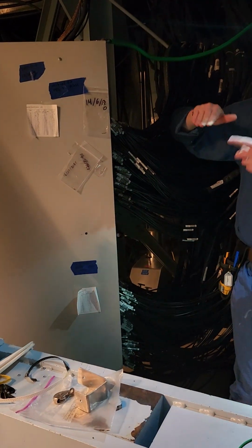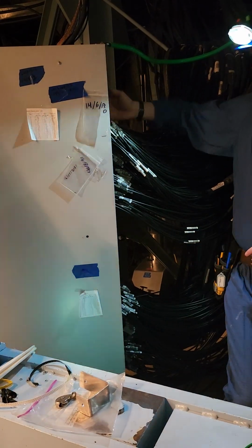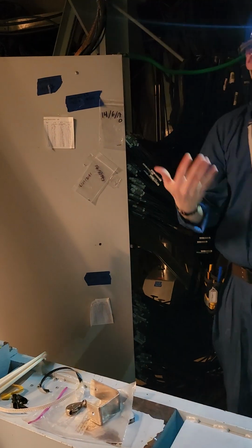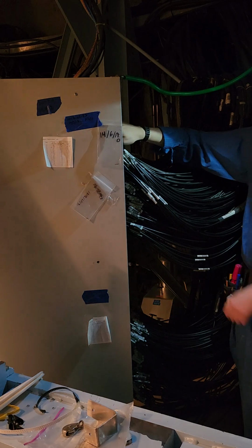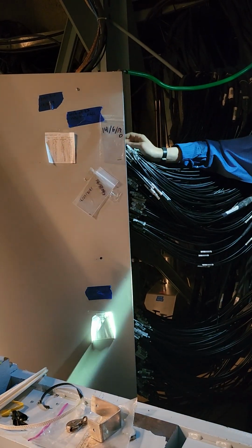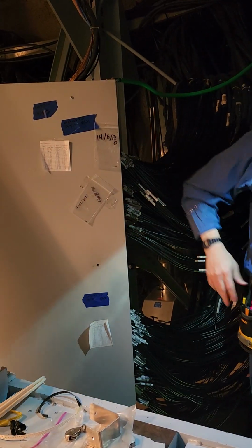You could document that and potentially make changes to update, but if we are going to do that, we're going to install things exactly as they are, because otherwise it will completely mess up the way that we expect the data to look. So if I were pulling all these out, that's why we write Sharpie marks on each of these, so we know which way they're supposed to go. And I'll write down markings if I do need to replace these. On the computational level, it's not that much of an issue.